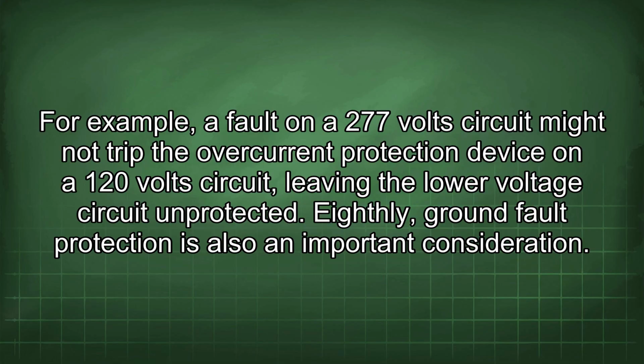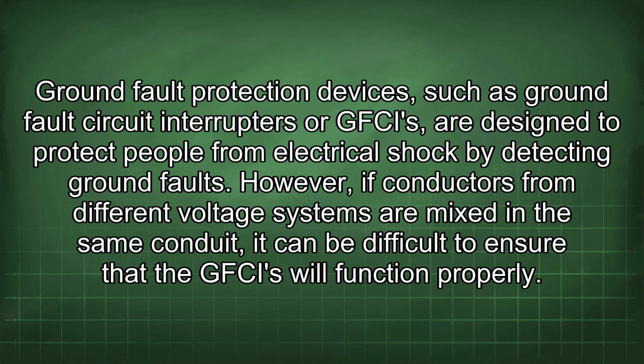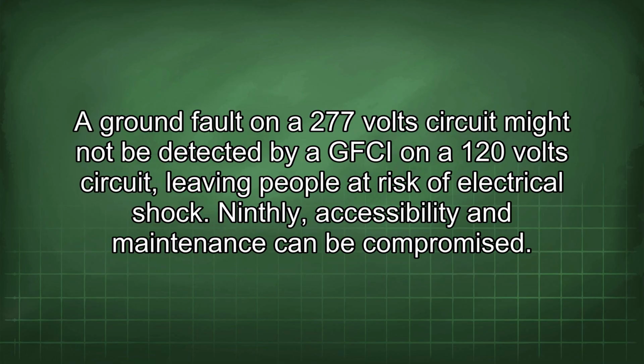Eighthly, ground fault protection is also an important consideration. Ground fault protection devices, such as ground fault circuit interrupters or GFCIs, are designed to protect people from electrical shock by detecting ground faults. However, if conductors from different voltage systems are mixed in the same conduit, it can be difficult to ensure that the GFCIs will function properly. A ground fault on a 277-volt circuit might not be detected by a GFCI on a 120-volt circuit, leaving people at risk of electrical shock.